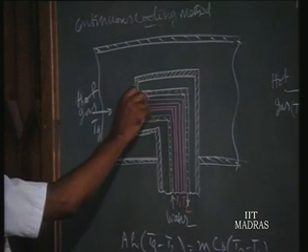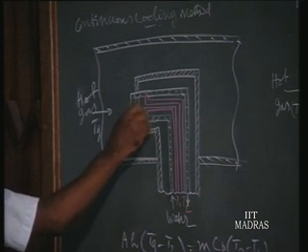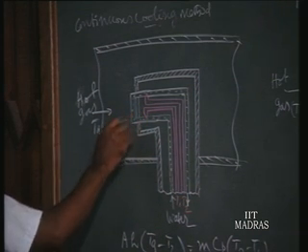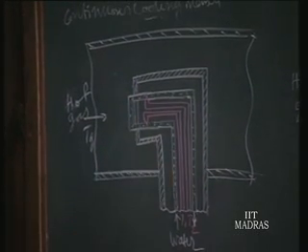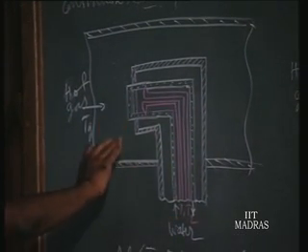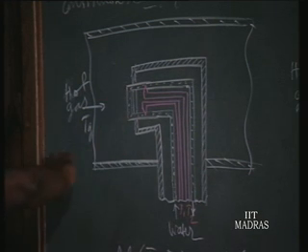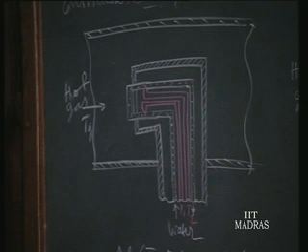So water gets heated up, and the water coming out from this section will have a higher temperature. These two temperatures, the inlet temperature before this heating zone and the outlet temperature from the heating zone, are measured using thermocouple wire, that is T1 and T2, which is a very low value. So this is what is measured. From these measured temperatures you can compute the hot gas temperature.